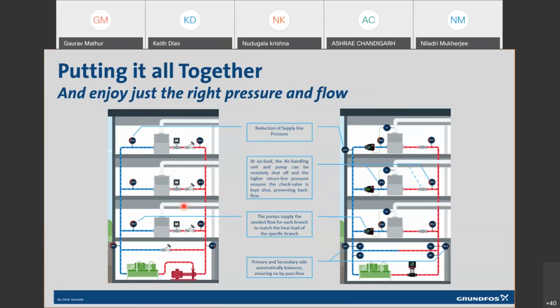Now, if we sum up the entire discussion which we have done up till now, what we see is the reduction of supply line pressure, because here you have a primary pump which is only producing water and taking it up till here. Now, there could be a very valid question: what happens here? So the water moves, it is like a supply header. The pressures are lower in the supply header on the secondary side and higher in the return header.